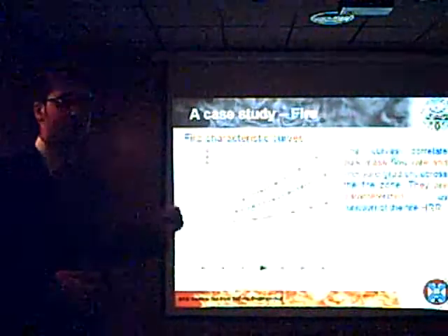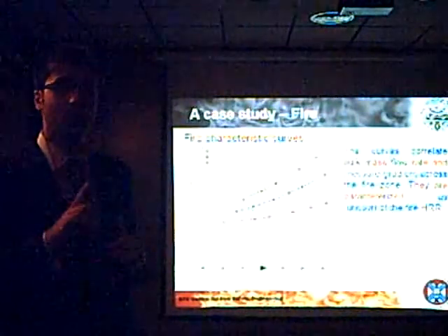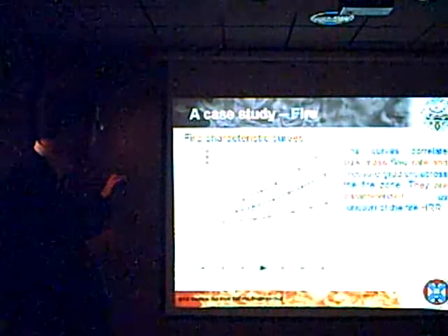So, depending on the fire size, we can get different curves. Obviously, the higher the fire size, the higher the pressure loss the ventilation system has to overcome. And in this case, for each fire scenario, we have two curves. The first one has been obtained with the temperature of the hot gas equal to 800 degrees Celsius, and the dashed line is obtained with temperature equal to 1200 degrees.